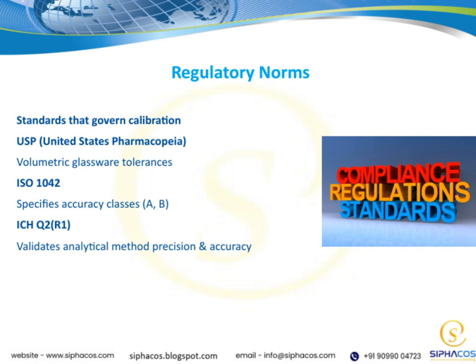Moving on, ISO 1042 is another important standard that specifies accuracy classes, namely Class A and Class B, to categorize the precision of volumetric equipment. This helps us understand the level of accuracy we can expect from different instruments. Lastly, the ICH Q2 R1 guideline focuses on validating analytical methods, ensuring that they are both precise and accurate. All these norms work together to uphold quality and consistency in calibration, which is at the core of our overall theme, maintaining high standards in laboratory practices.